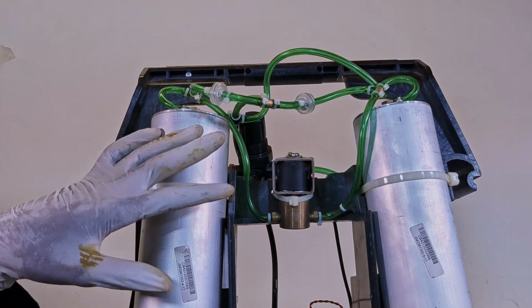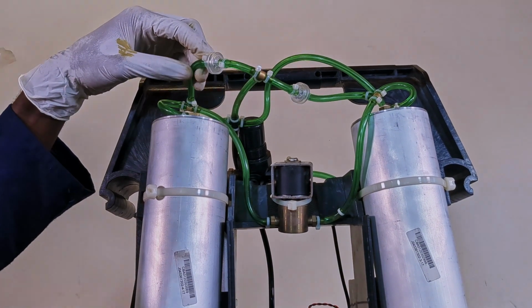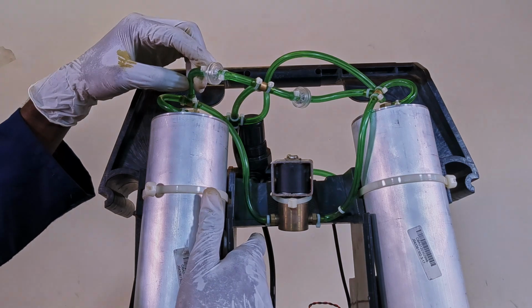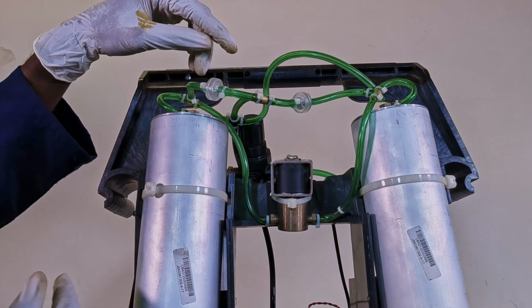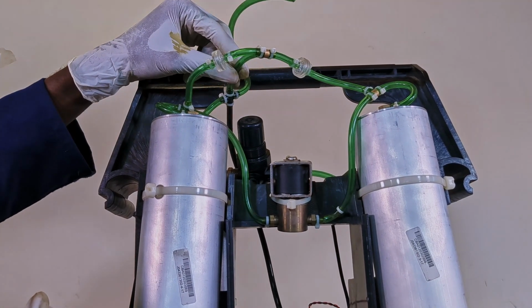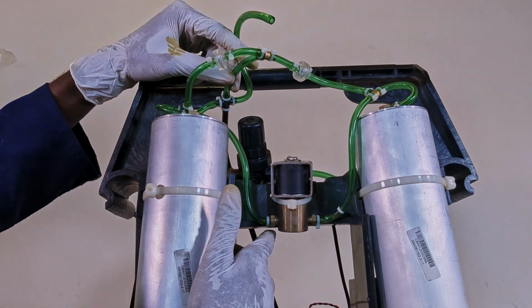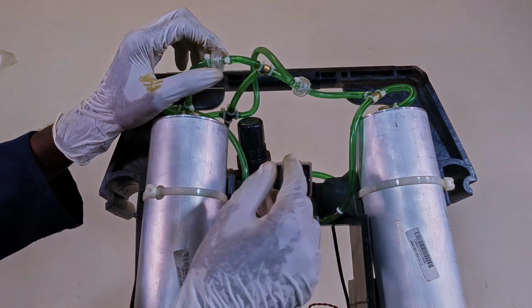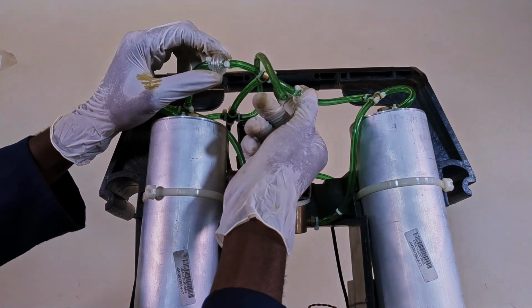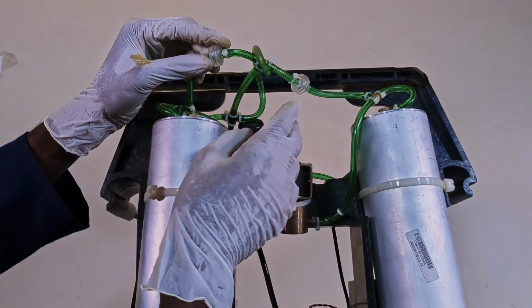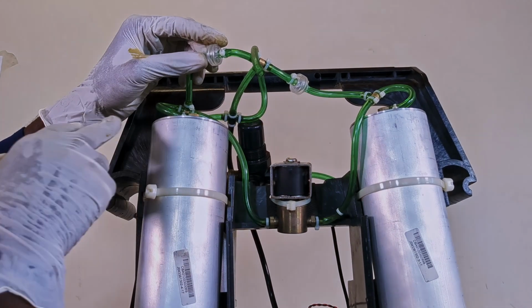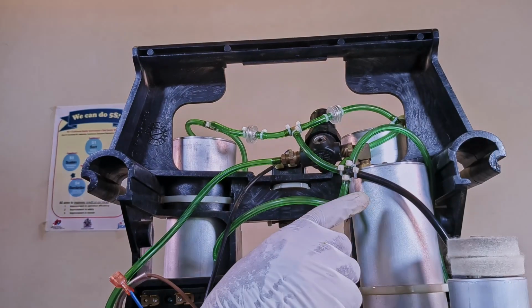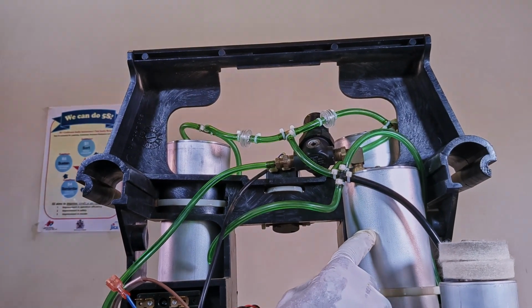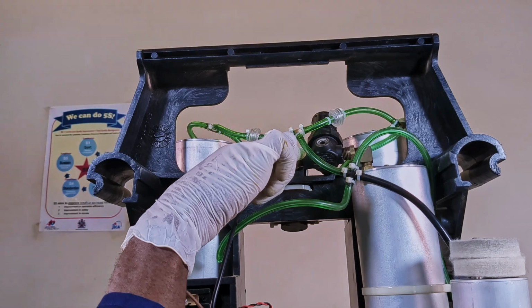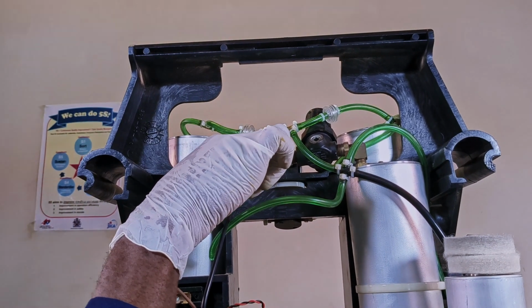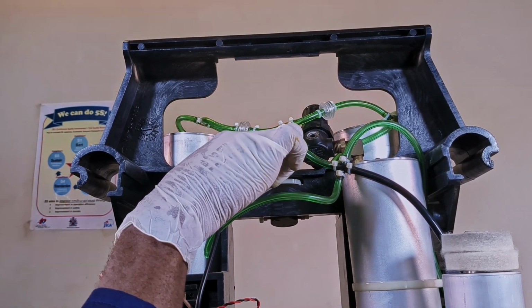From the sieve beds, oxygen passes to the accumulator tank or the product tank. So oxygen passes through this tubing to the accumulator tank. This check valve and also another one on the other bed prevent the backflow of oxygen as it flows to the product tank. From the product tank, oxygen passes through the pressure regulator. This regulator ensures that oxygen is delivered at a constant pressure of 20 psi.